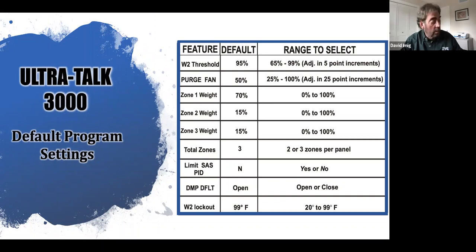And my W2 lockout, which is important in some states where it's code, is a temperature that says you cannot bring on auxiliary if the temperature is X or higher. So you have to know where that number is, and that's the number you plug in there. It means they want you to utilize the heat pump at this temperature and below. Do not bring on auxiliary if it's above 50 degrees or 60 degrees, whatever that code says.